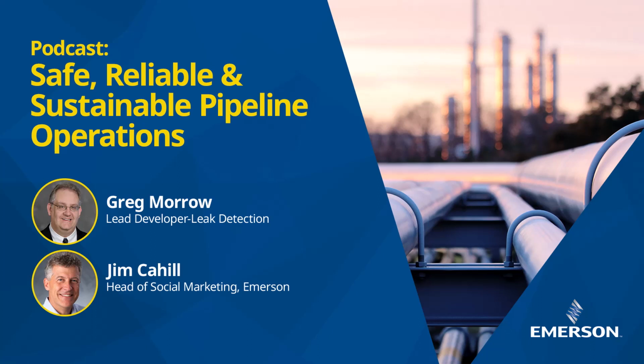Well, that's interesting. I noticed that that's the second time you talked about sensitivity, reliability, and some of those other things. Is there a reason for that? So those are terms from API 1130, which is a document that discusses computational pipeline models, or CPM, like the RTTM. And they're particularly useful terms for evaluating leak detection systems.